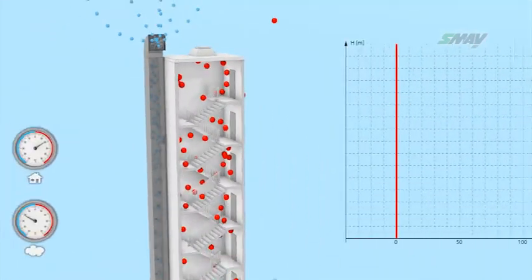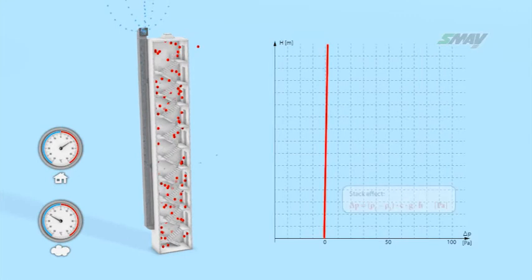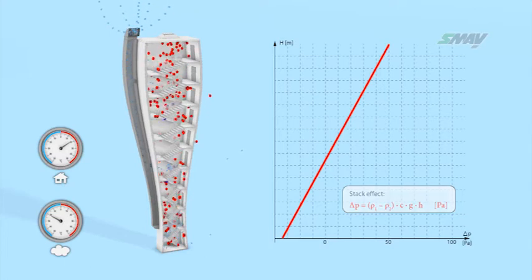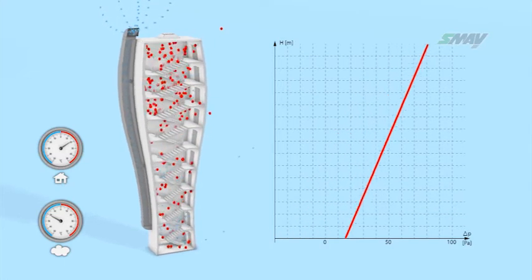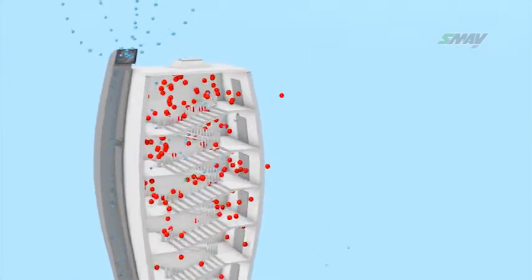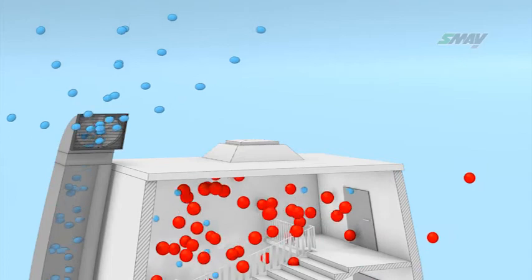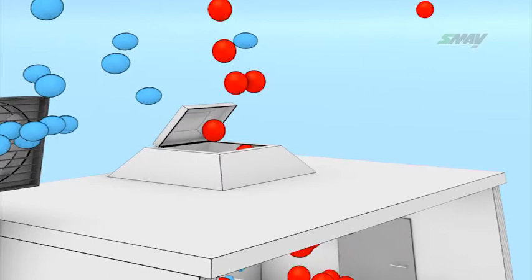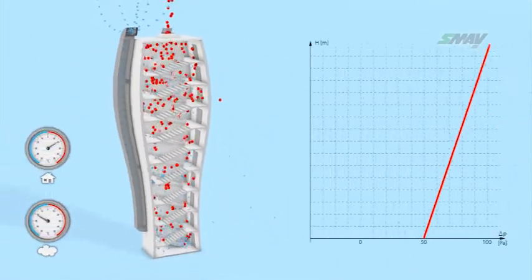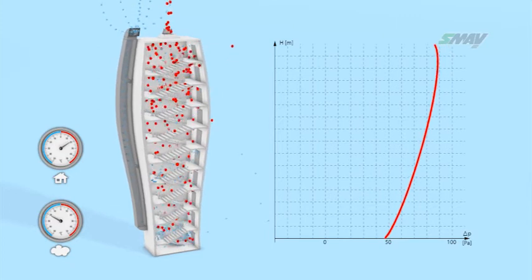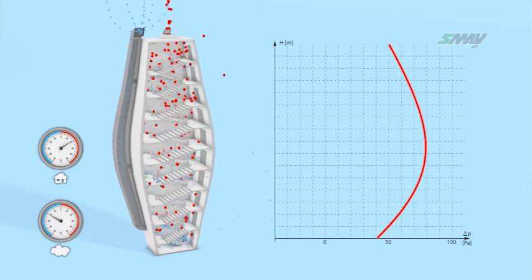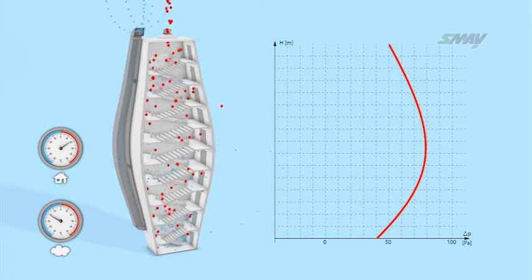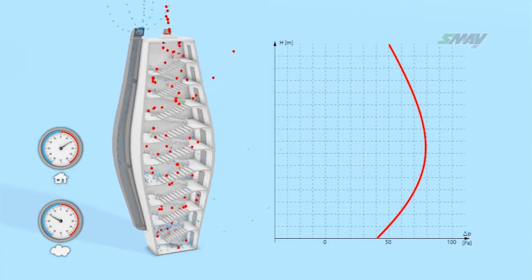However, if in this case air is supplied to the stairwell at a temperature significantly below that of the inside, then pressure stratification will occur as a result of the stack effect. The supply of large amounts of air causes a rapid increase in pressure, but the increase will not be uniform across the entire height of the stairwell. The stack effect will disturb its distribution. A pressure increase in the upper parts causes the barometric overpressure dampers to open, maintaining pressure at no more than 50 pascal. Once the barometric overpressure dampers open, pressure in the entire stairwell changes and its value is equal to the resultant of the flow resistances, relative to the size of the airstream and the stack effect.